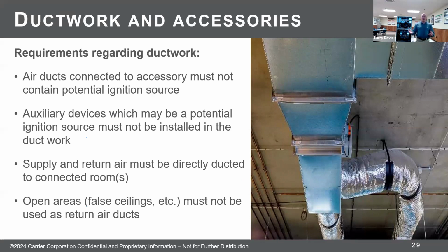And you'll see how that works. We turn the fan on and circulate the air because our coil sits inside the airstream. So we're going to use that movement of air to get rid of the refrigerant and to mitigate that. For that reason, we can't have anything in the duct system that can be a potential ignition source. So we'll see how that works here in a little bit.